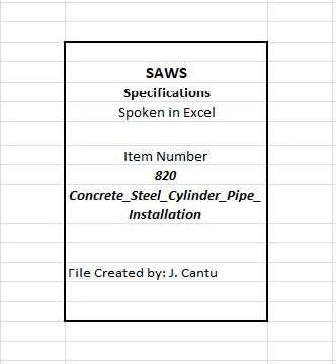B. Test cylinder/joint ring weld for tensile strength. C. Reject dented steel cylinders. 19. Prestressing wire. A. Inspect wire spacing during wire placement on core. B. Test wire splices for each production run.